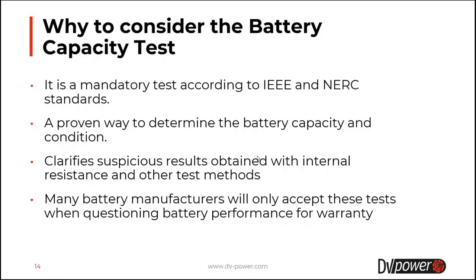Actually, there are standards dictating that you have to perform internal resistance tests, and if you get a resistance result with values higher than before, you have to perform a capacity test in order to know whether to remove the battery or not. Many battery manufacturers will only accept battery capacity tests when questioning battery performance for warranty.